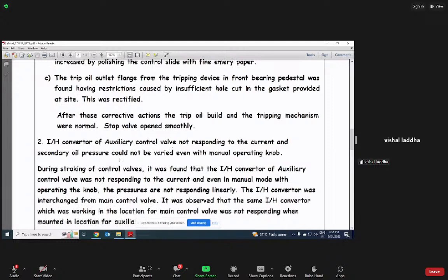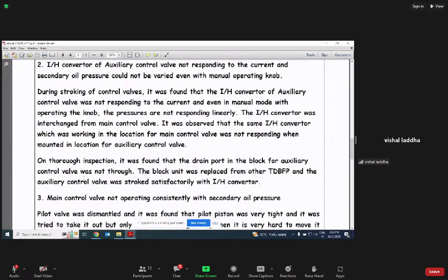I2H converter of AGV, auxiliary governing control valve, not responding to the current and secondary oil pressure. During stroking of the control valve, it was found that the I2H converter of AGV was not responding to the current, and even in manual mode, when operating with the knob, the pressure was not responding. So what action was taken?